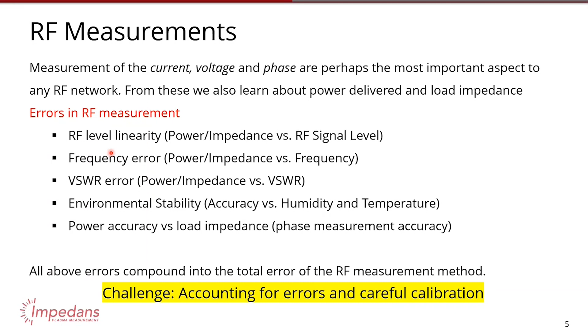There are many sources of error in RF measurement: the linearity of the measurements versus the signal or power level, the frequency errors - what are the measurements like versus frequency, what are measurements like versus VSWR, what about the temperature of the sensor you're using, the local humidity, and so on. And power accuracy can change with load impedance. So RF measurements are actually quite complicated. Let's start off with the most simple measuring device, the directional couplers.